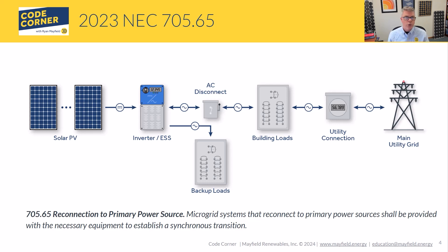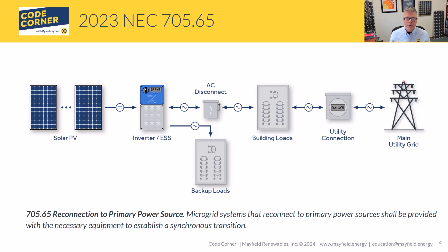On larger scale systems, you may achieve this through relay systems, motorized breakers, or contactors — there are multiple ways to accomplish this. A big part of it comes down to what the utility allows. Regardless of the method, the microgrid system must establish that synchronous transition, which is one of the key requirements to be truly a microgrid system adhering to Article 705.